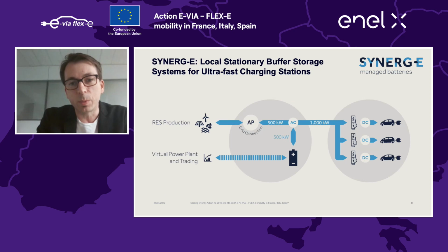We put a battery between the grid connection and the high power charging stations in order to provide peak shaving for the charging station, limiting the amount of energy and power consumed from the grid via the normal grid connection. At the same time, in periods with less traffic and fewer charging events at the location, the battery can provide flexibility for the energy markets and for system services like primary and secondary control.